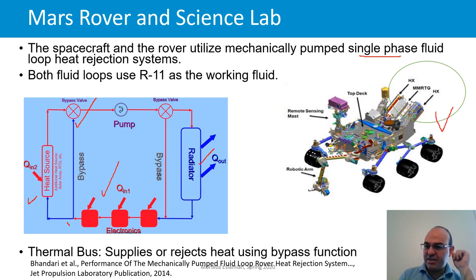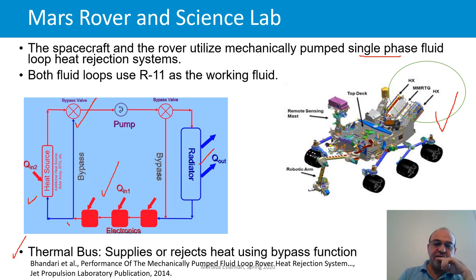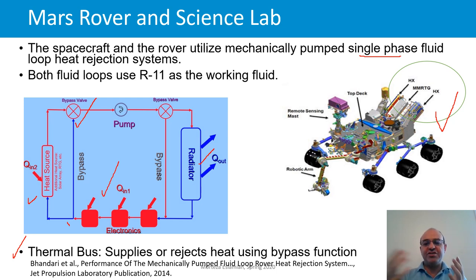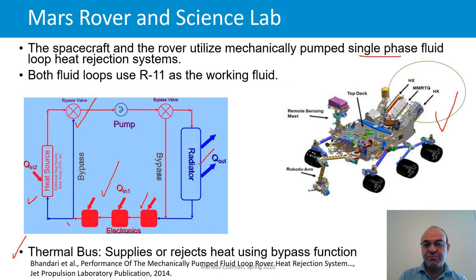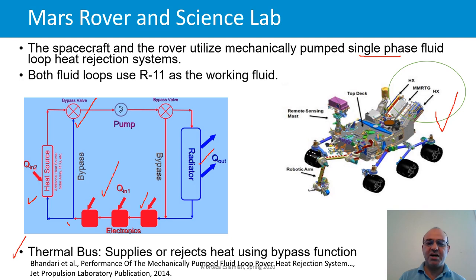This system is also called a thermal bus because it supplies or rejects heat using a bypass function — like a bus where people can get on and off. The fluid loop distributes and shares heat between different components: if one component generates a lot of heat and another needs heat, that heat can be shared. The heat-sharing capability, or thermal bus function, is one key advantage of the pumped fluid loop.